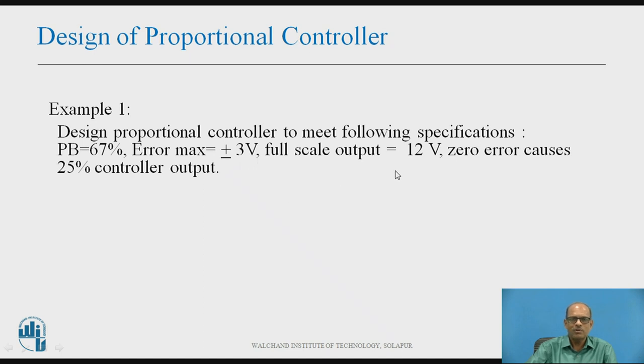Now, design of proportional controller. Let us take this example: design a proportional controller to meet the following specifications — proportional band equals 67%, error maximum plus or minus 3V, full scale output equals 12V, and zero error causes 25% controller output. This is the design task given.